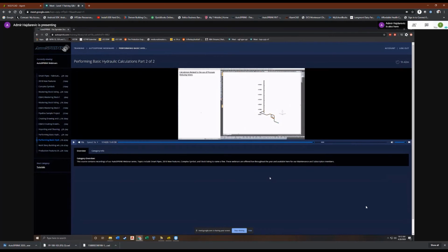Now, assuming that the inlet pressure is greater than the valve setting, so let's say your available pressure is 220 psi and the valve setting is 165, then the pressure loss through that PRV is just the difference between the valve setting and that available inlet pressure. Where it gets tricky, and I don't think you're necessarily going to run into this scenario for this low pressure or low zone, is when the available inlet pressure is below the pressure setting of the valve.